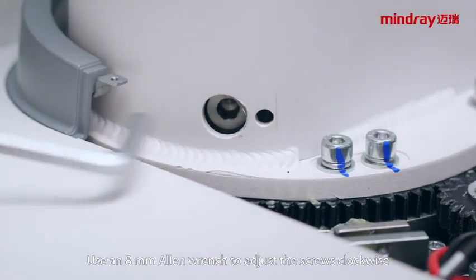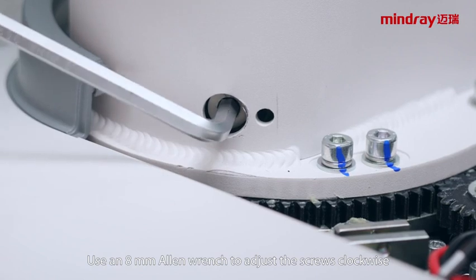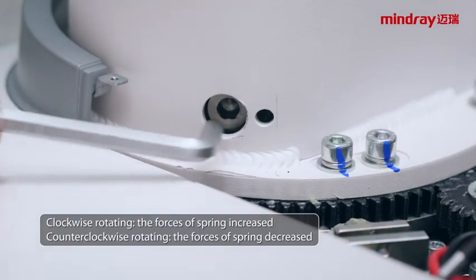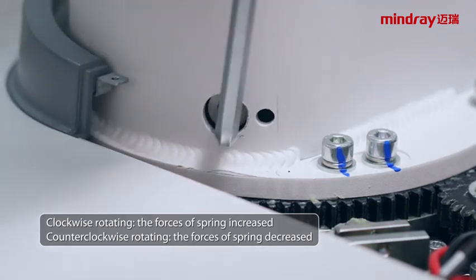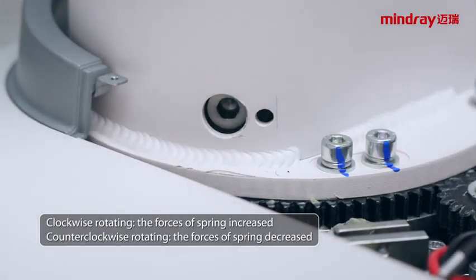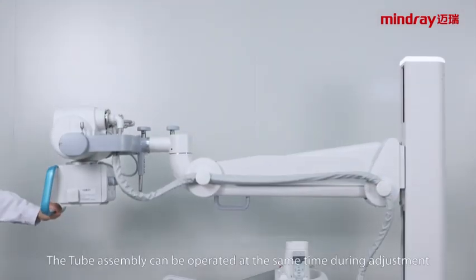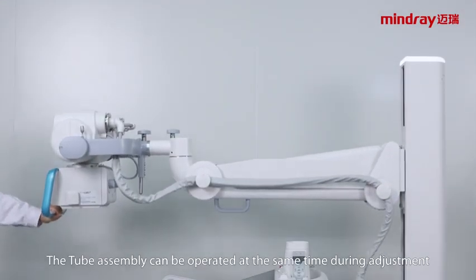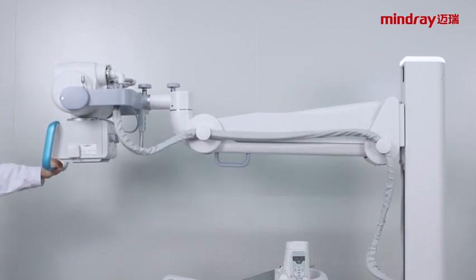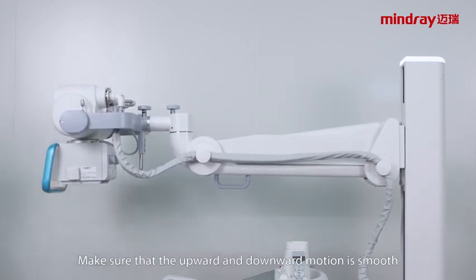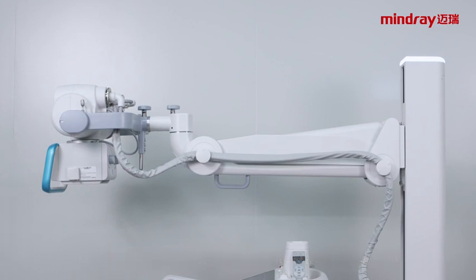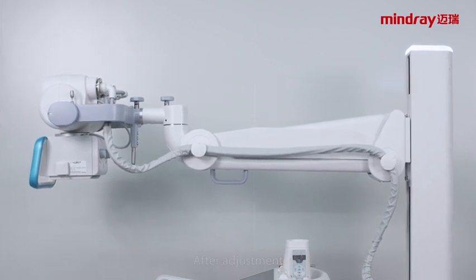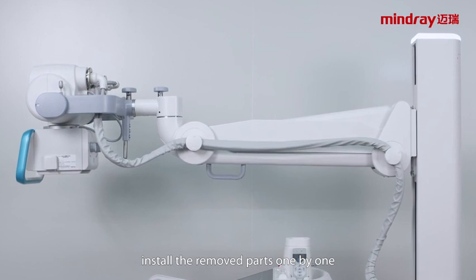Use an 8mm Allen wrench to adjust the screws clockwise. Rotating clockwise, the force of the spring increases. Rotating counterclockwise, the force of the spring decreases. The tube assembly can be operated at the same time during adjustment. Make sure that the upward and downward motion is smooth. After adjustment, install the removed parts one by one.